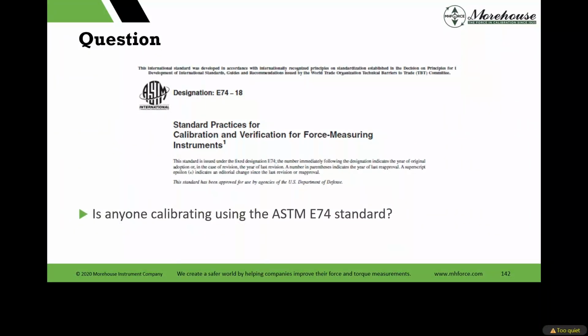So I did ask for some comments there, and some good comments on these. Okay, I have realized that you are mostly focusing on load cell calibrations. In my case, I calibrate force machines. Yeah, it is mostly load cells in this, but there are some takeaways for force machines because you're using the load cells that were calibrated to go calibrate those force machines. So some of this applies, the E74 stuff, and having the background and knowledge of that should help. But yeah, I'm not talking about a lot of the E4 stuff.